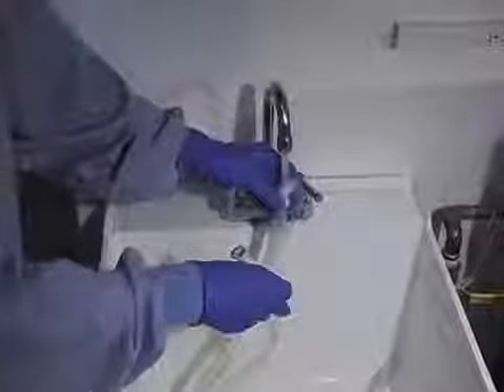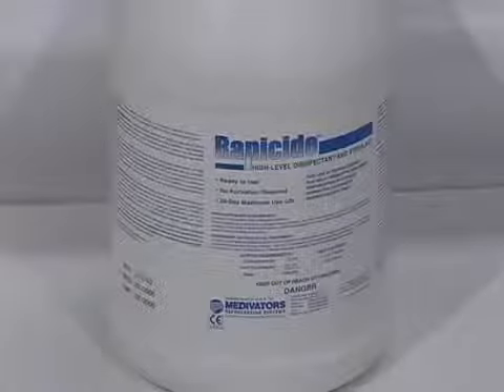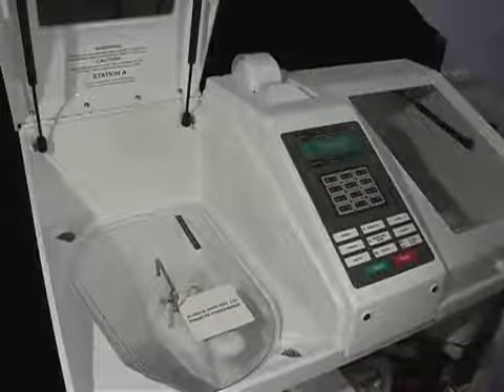After the reservoir has been filled by the onboard transfer pump, rinse the feeding tube with water. Do not kink the tube during storage. Rapicide requires no activation, but it may take up to 2 hours to heat up to the required 38 degrees Celsius in the reservoir. Now let's demonstrate the other method for loading disinfectant through the basin. This may be your preference.